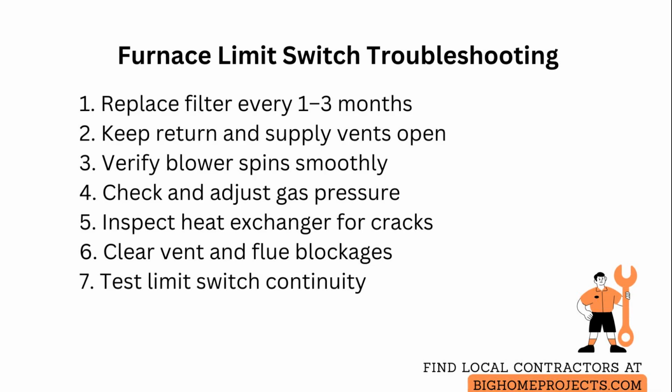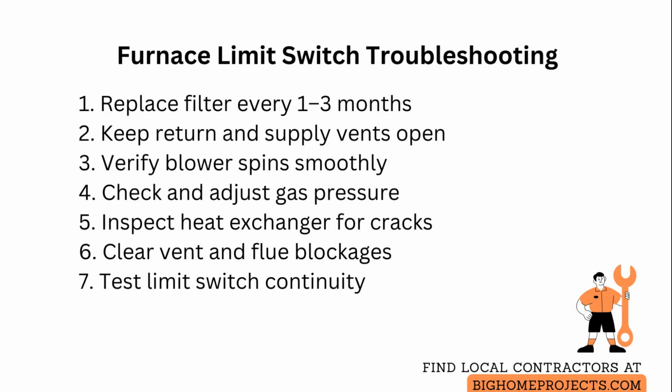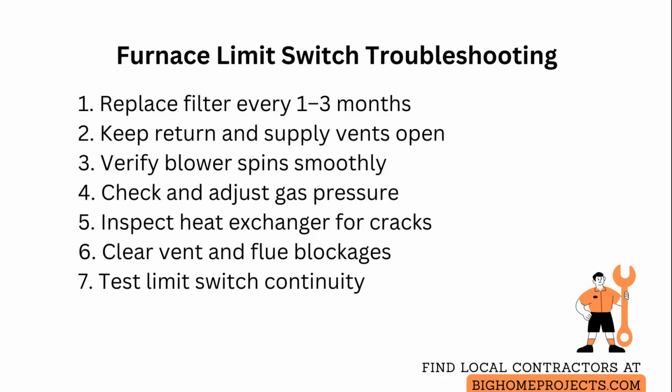High gas pressure or improper burner adjustment can force excessive heat production. So measure manifold pressure or have a qualified technician tune the burner and check the gas regulator for correct settings.